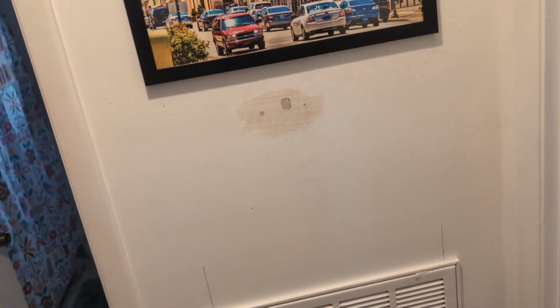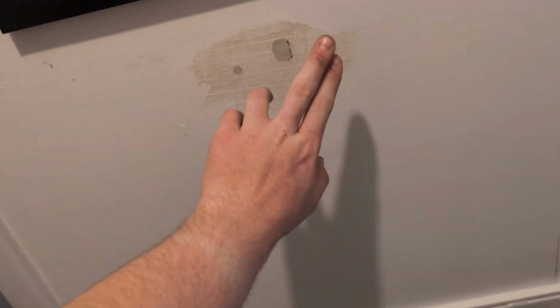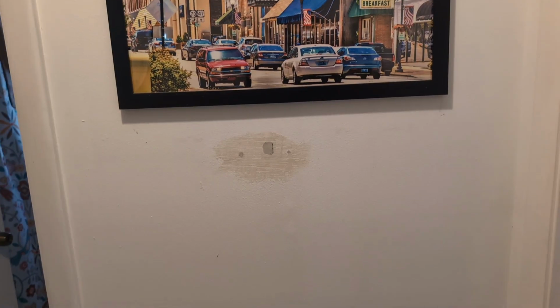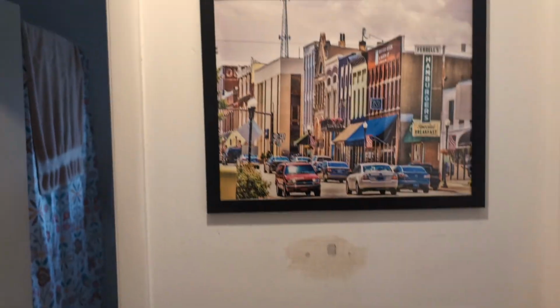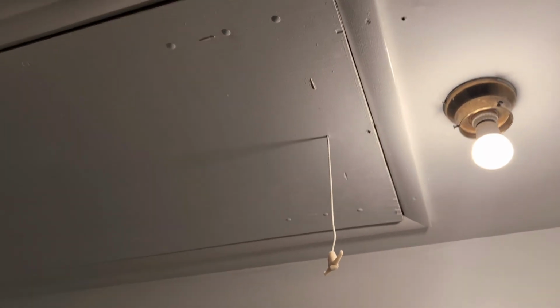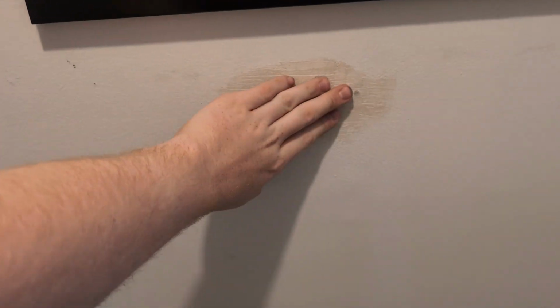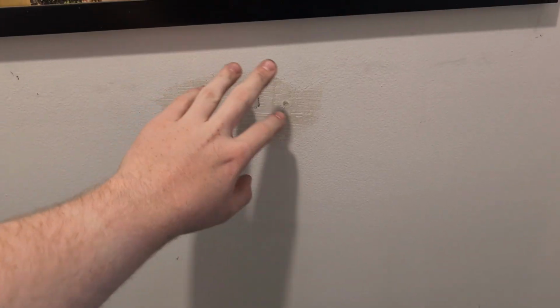So this thing was running way too long and subcooling the house to around 65 degrees, even though the thermostat would be set to 72. You couldn't offset it to correct it because it entirely depended on what temperature the attic was. If it was a sunny day outside and really hot, the attic would be super hot, causing the air to be hotter, which would make this thermostat read even more incorrectly. On a day like today, it'd be relatively correct.